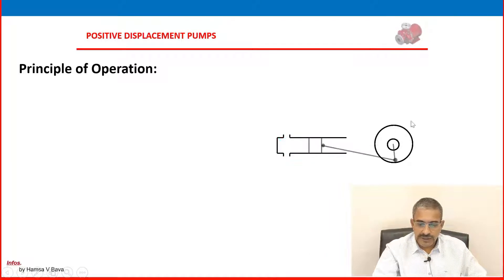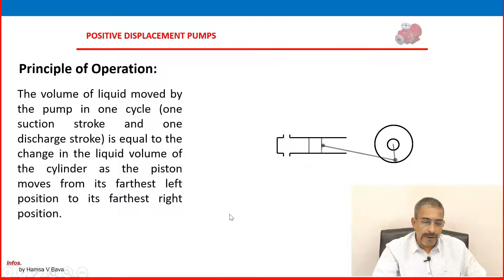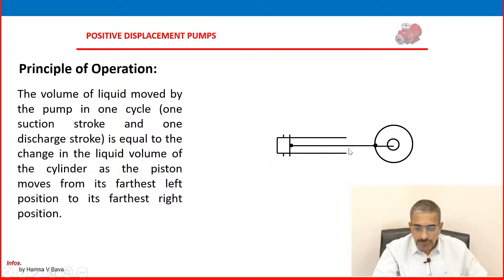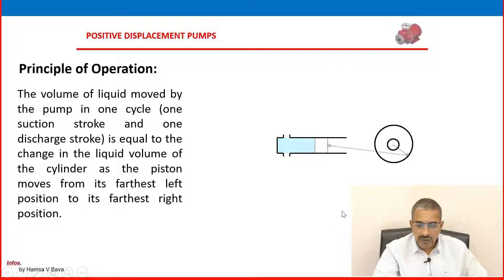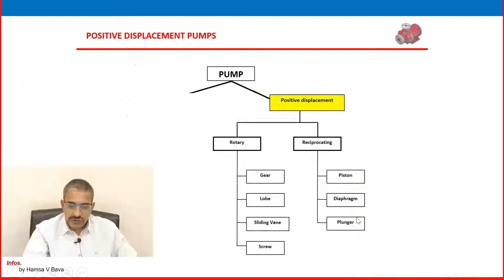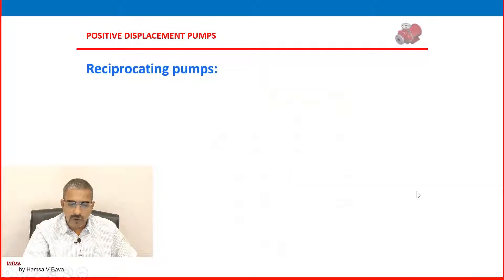Continuing the principle of operation: this is the driving mechanism and this is the pump area. The volume of liquid moved by the pump in one cycle — one suction stroke and one discharge stroke — is equal to the change in the liquid volume of the cylinder as the piston moves from its farthest left position to its farthest right position. Liquid is entering and leaving using the suction stroke. The piston moves to and fro inside the cylinder, driven by the driving mechanism. In the reciprocating pump category, we will go further into reciprocating pumps.